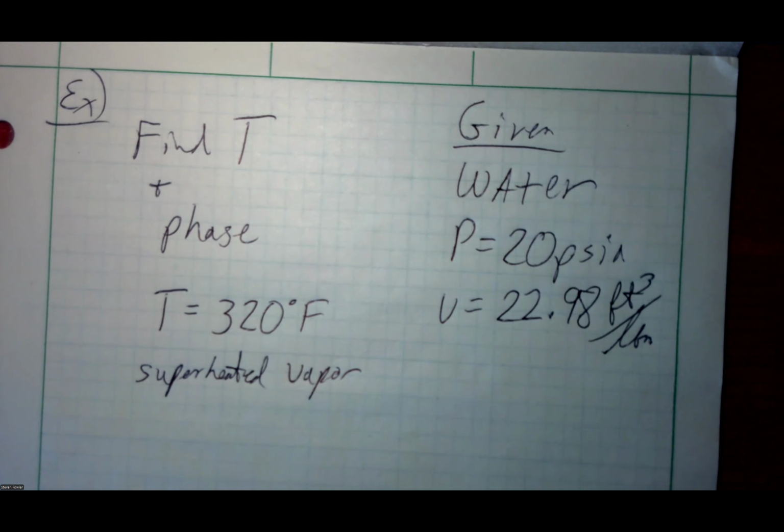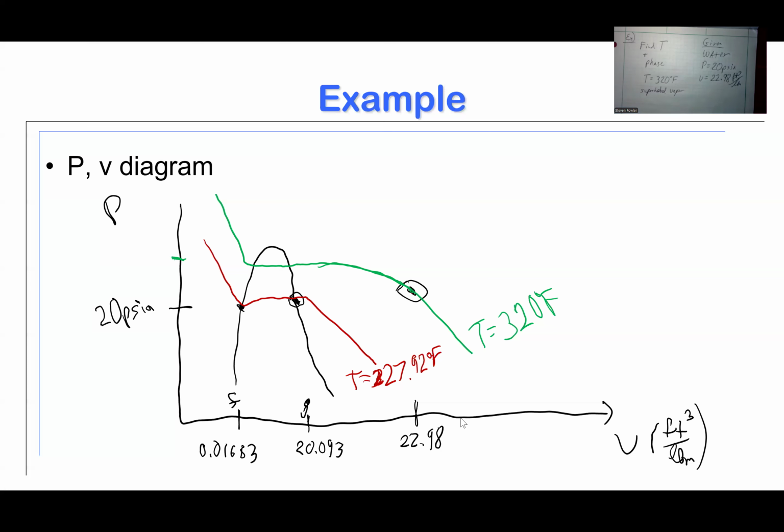So 89.667 psi is what we're going to put on that chart then. So share my screen back here and bring PowerPoint back. That is 89.667 psia. That is the corresponding pressure for this temperature of 320 degrees Fahrenheit. So you can see it's not a pretty graph. It doesn't have to be. It just needs to get your point across.